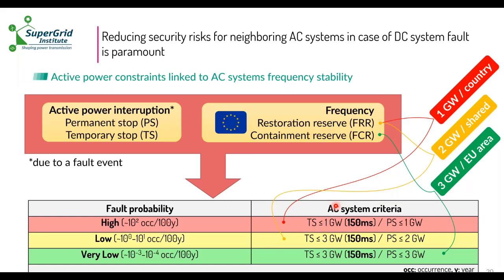But since here we're talking about design of the protection system, you have to take into account the surrounding transmission system, which is the AC system. And so you need to define a framework based on the active power interruption and the impact on the frequency reserves, because you need at the end power to compensate the interruption of this active power, which is taken from the restoration reserves, FRR, and the containment reserve, FCR. So here you need to match high probability fault scenarios to low AC system threshold. For example, if the stop is temporary and lower than 150 milliseconds, so you have a high probability fault, you can use up to 1 gigawatt of the restoration reserve.